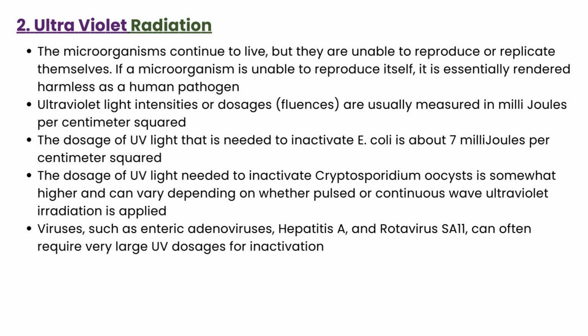The dose of ultraviolet light needed to inactivate E. coli is about 7 millijoules per centimeter squared, while viruses such as enteroviruses, adenoviruses, hepatitis A and rotavirus SA11 can often require very large ultraviolet doses for inactivation.